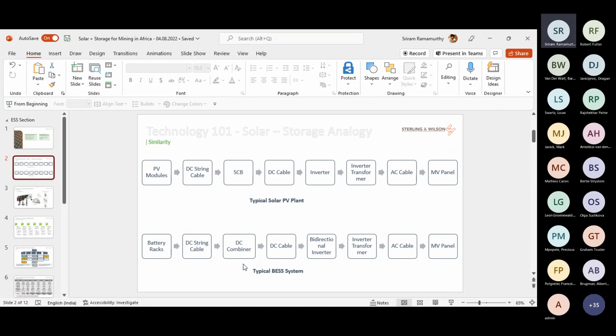Right. We have a DC combiner after that, then the bidirectional inverter or PCS, then the transformer, the AC cable, and the MV panel. All this has to be added depending on the C rating. Fundamentally, for a 1C application, if you're doing a 1 megawatt hour plant, you're also doing a 1 megawatt PCS, meaning the DC to AC ratio is 1. Then obviously the inverter cost increases.